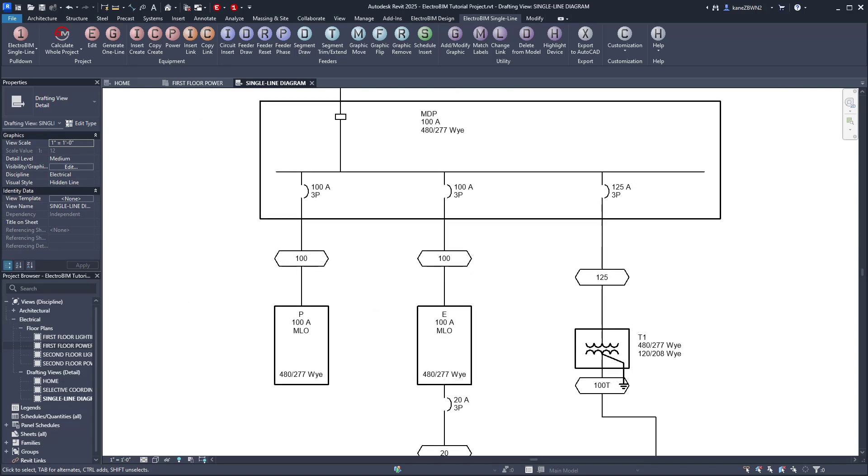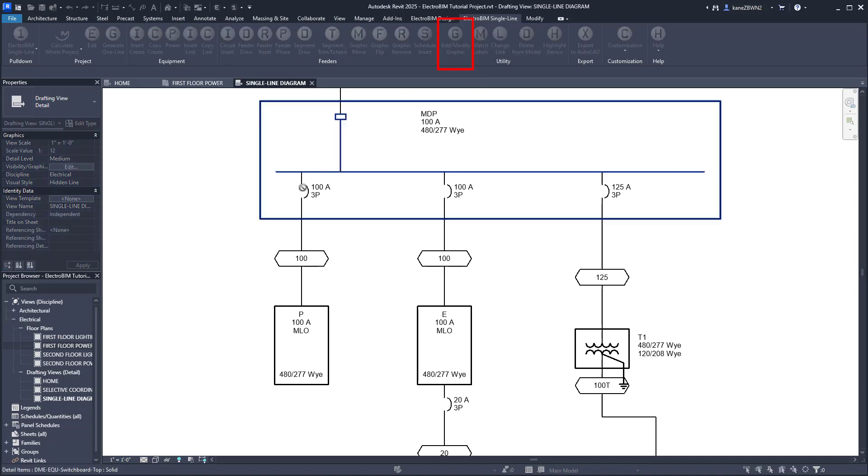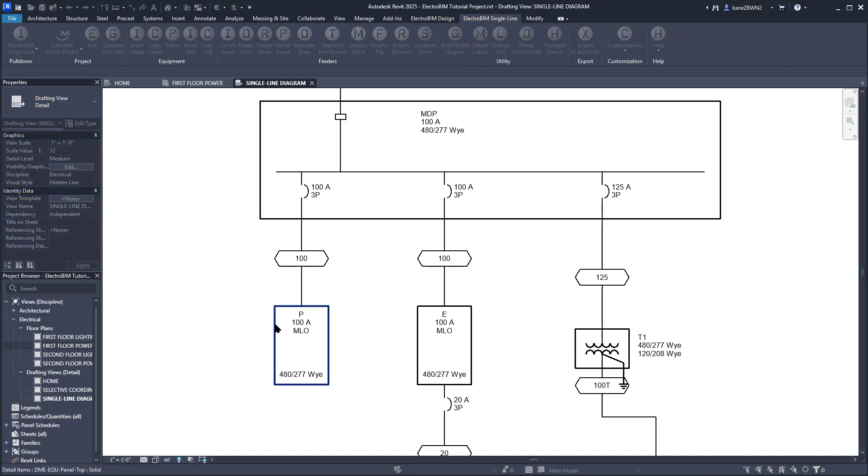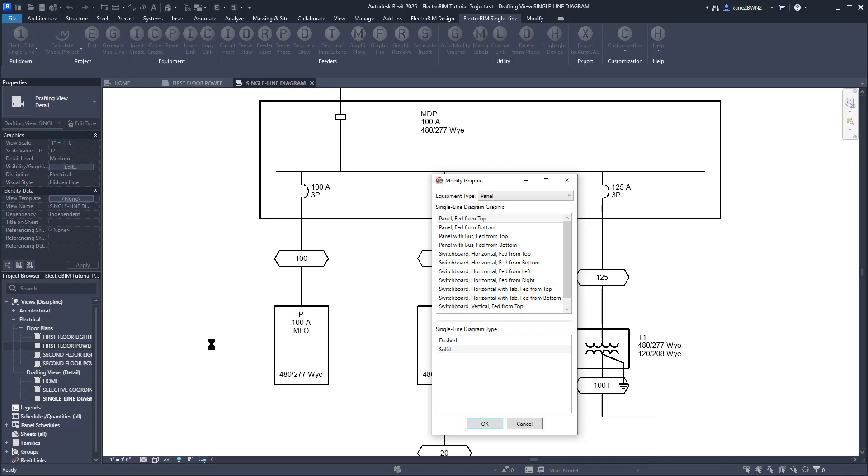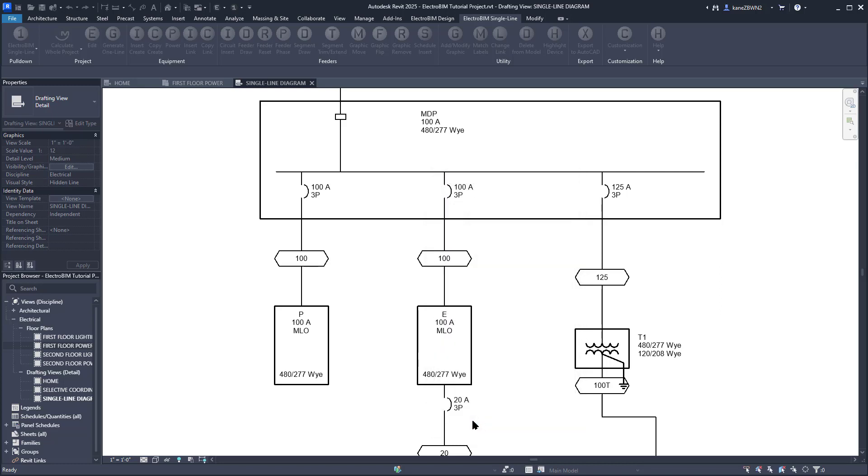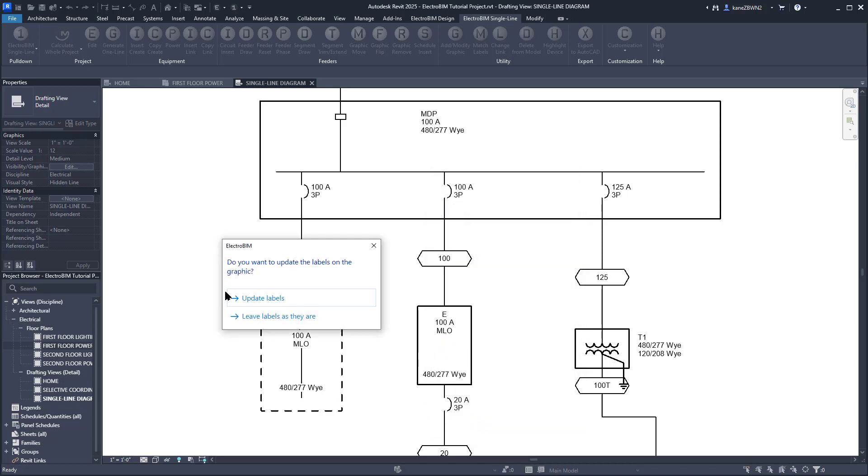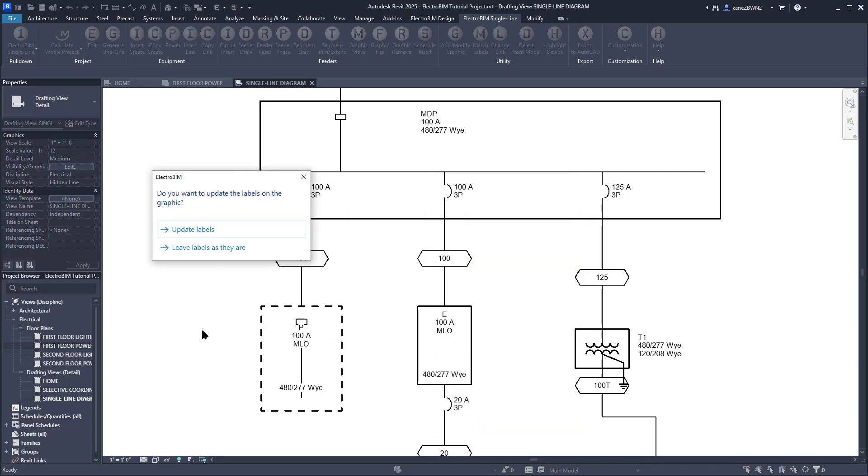Next, we're going to change how some of these graphics look using the Add-Modify Graphic command. We'll select Panel P, and it will give us those graphic options we saw earlier when we were inserting it initially. Let's do Panel with Bus fed from top, the dashed type. Press OK, and you can see the changes there. Because that graphic usually comes in with different labels than the previous graphic, ElectroBIM will ask whether you want to keep the labels and placement you have, or get new ones. We'll select Update Labels to go with the new stuff.